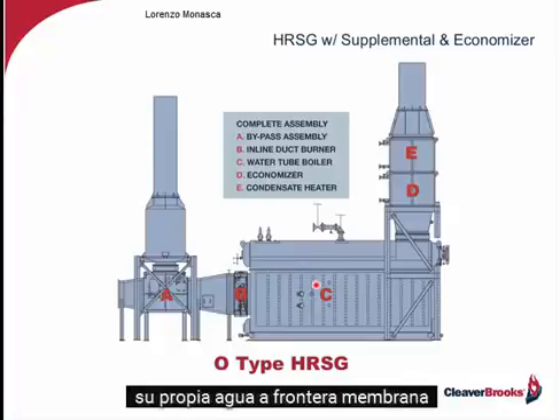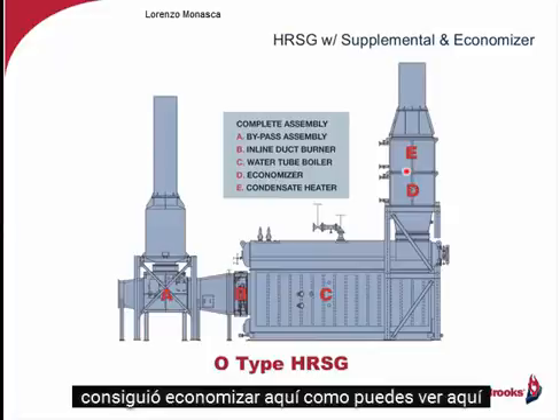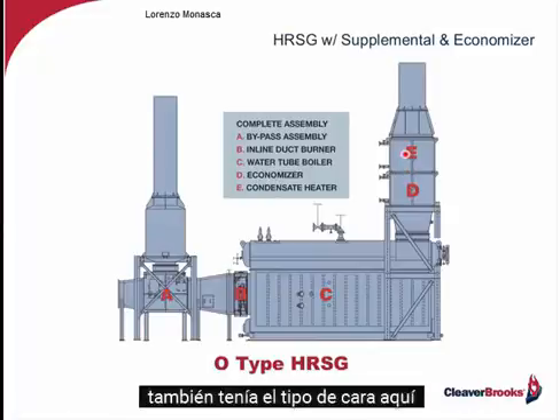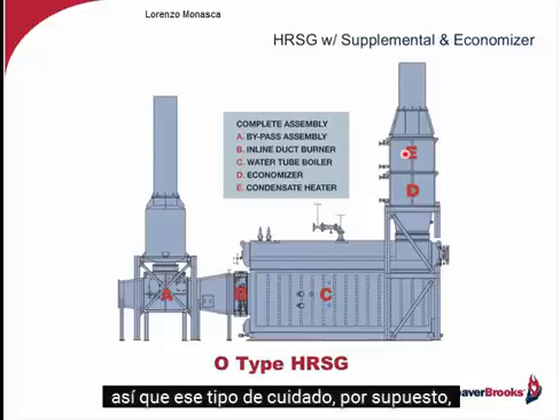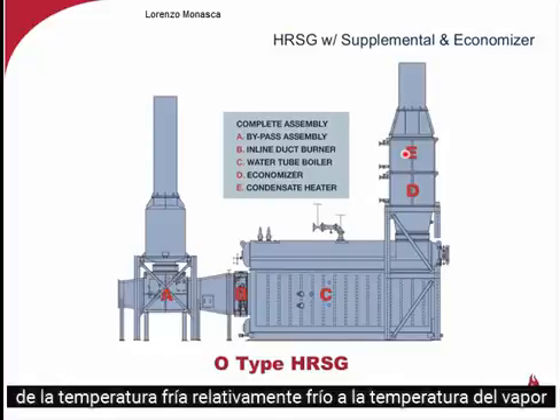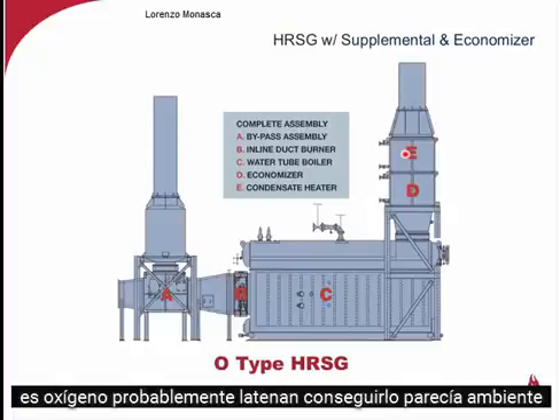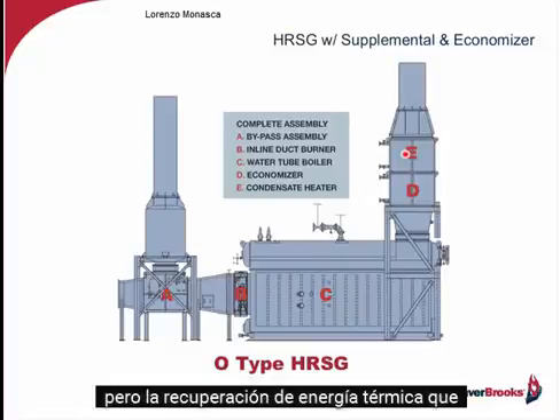It's a water tube boiler. It's membraned. It's got the economizer, as you can see here. And it also has a condensate heater to absorb additional BTUs that would normally go out the stack. So that condensate heater, of course, we've got condensate coming back at a relatively cold temperature, relatively cold to the steam temperature. It's probably laden in oxygen because it's seen atmosphere. So it's got to be heated before it goes into the deaerator, but recovering that thermal energy.